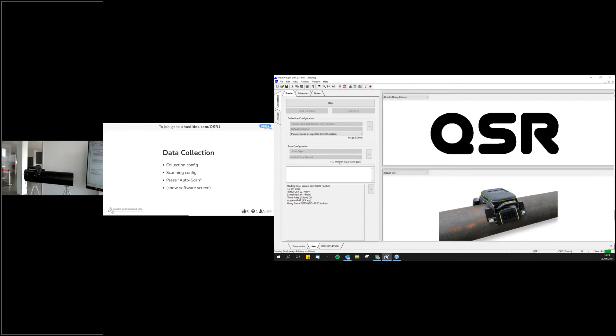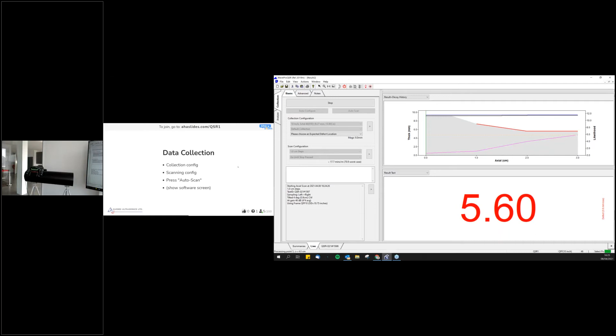Okay, so the QSR1 has started scanning. Notice that it is moving semi-automatically. On the right-hand side, in the software, you will start to see a plot of thickness in millimeters against axial distance. Zero represents the start location of the QSR1, and the rest of the distance from there in the positive direction represents the numbers on the x-axis. Just to give a bit of insight on the pipe that we're inspecting here today, we are expecting to detect and size 3 different defects.